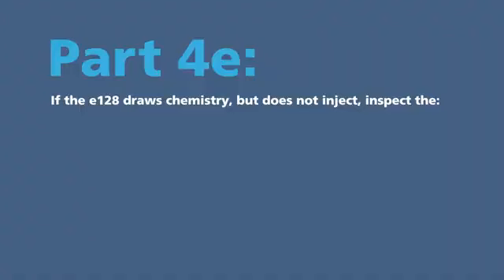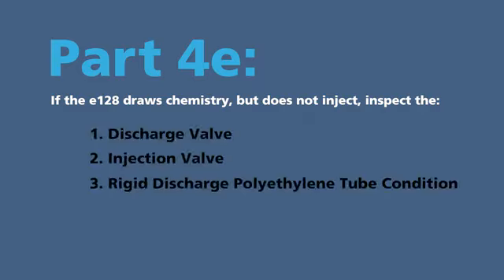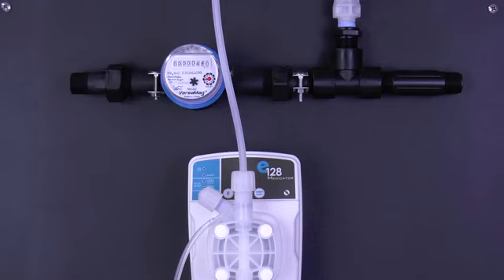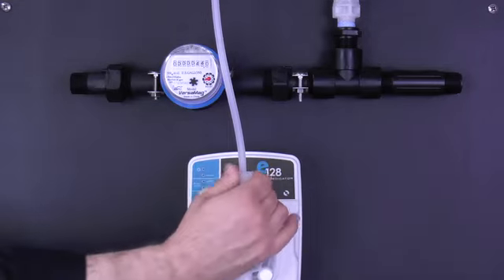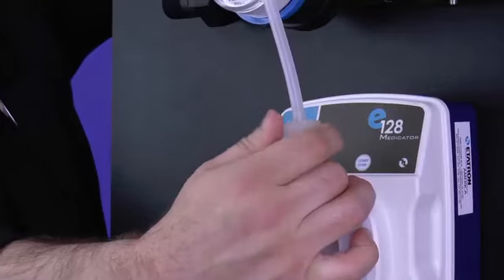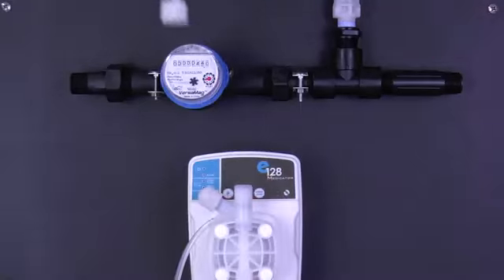Part 4E. If the E128 draws chemistry but does not inject, inspect the 1. Discharge valve, 2. Injection valve, 3. Rigid discharge polyethylene tube condition. Discharge valve. Start with the discharge valve at the top of the pump head. Loosen the discharge valve tube nut and lift the discharge tube, nut, collar, and nozzle attached.